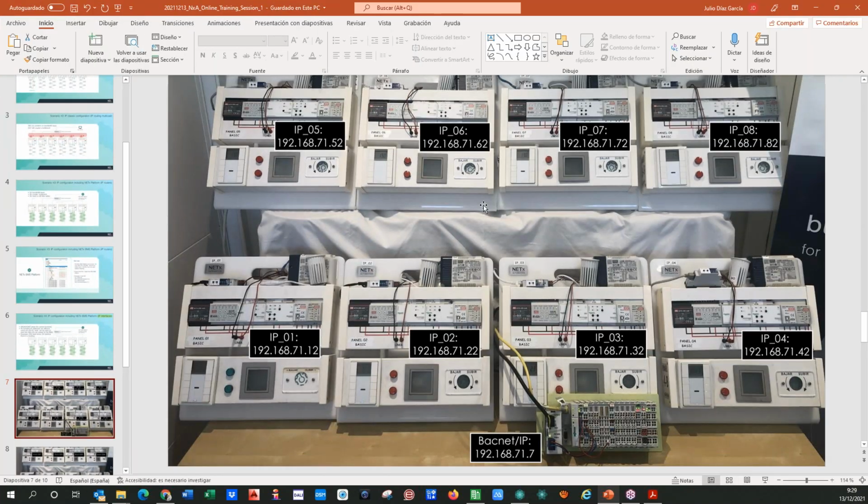It's very simple. I will do two different examples for you to understand. Imagine that we have these 8 panels and these practical boards. I will show you again so you remember. Imagine you have this as IP routers. This is the device here. The IP interfaces are these devices that you can see here, for every practical board. Imagine that you will have IP routers, so you have the communication between the lines with no problem because you have filter tables here controlling this. The BMS will use the tunneling connection, so you will have 8 different tunneling connections.